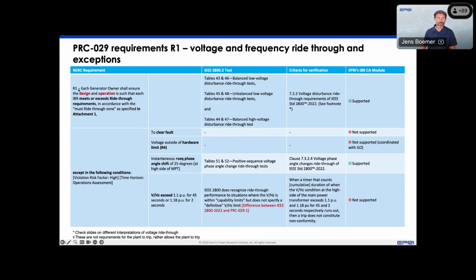So in general, for requirement 1, which is both about design and operation of the IBR to meet the ride-through requirements, the IEEE 2800.2 framework provides tables that test for balanced low voltage disturbance, for unbalanced low voltage disturbance, and for balanced high voltage disturbance. And IEEE 2800 clause 7.2.2 has the specific requirements. So all of that is supported in the EPRI tool and probably some other tools as well. Now there are exceptions to this requirement to clear fault, for example, and that's an exception that is currently not supported by our tool.